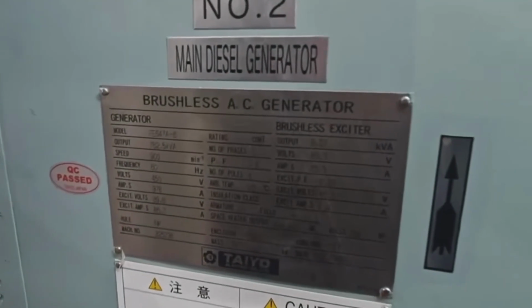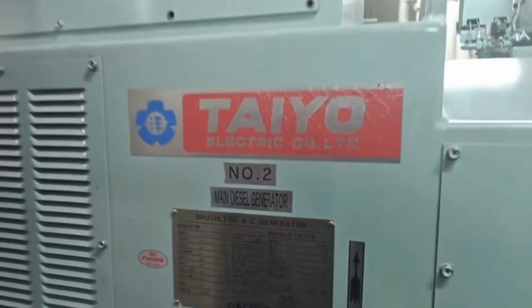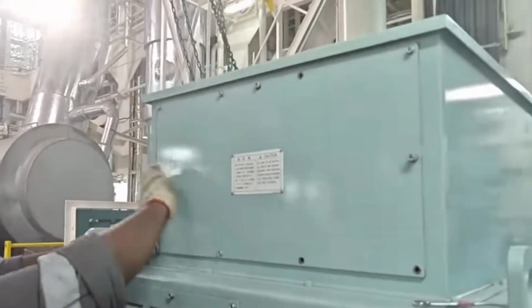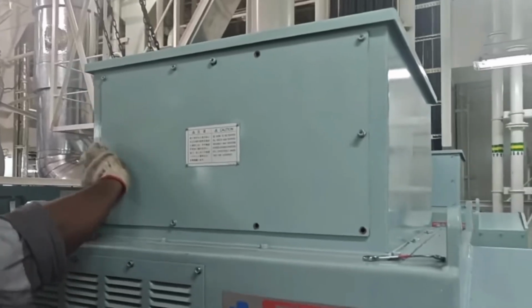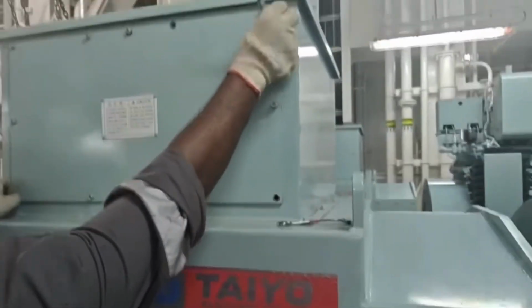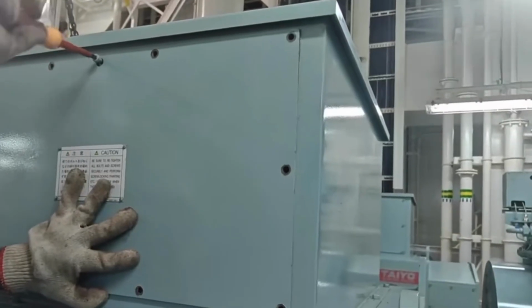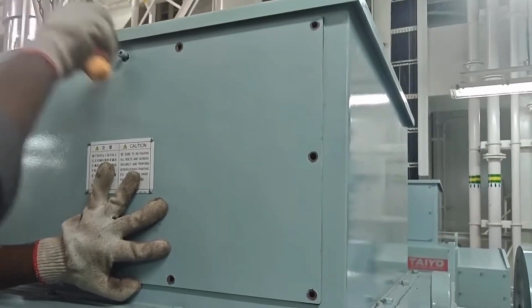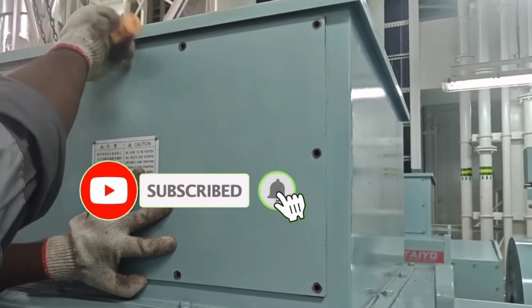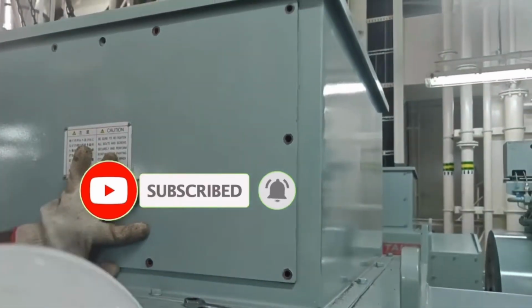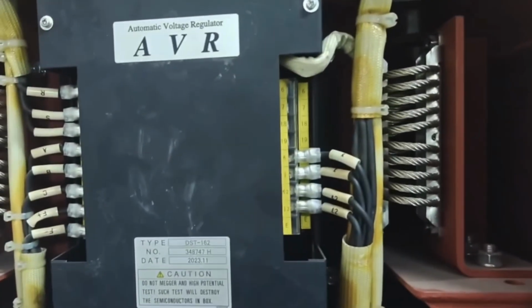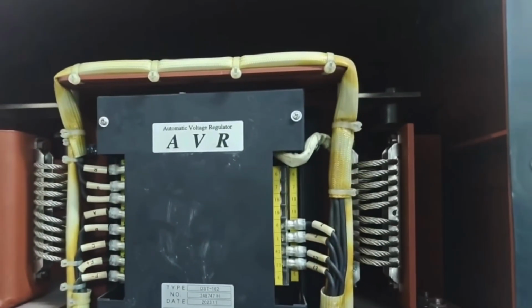A key component in this stage is the automatic voltage regulator, or AVR. The AVR controls the output voltage of the alternator, ensuring a stable and consistent power supply under varying load conditions. Engineers perform detailed AVR checks and calibration, adjusting voltage levels, response time, and protection settings. This ensures the alternator can respond instantly to load changes without fluctuations or instability.